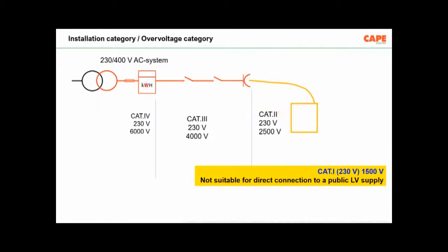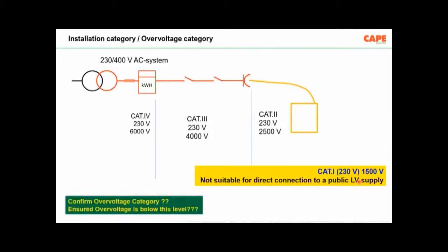That means in your wiring, the minimum category of the equipment is category 3. Connected equipment is category 2. There is equipment called category 1, that means highly sensitive electronics. These highly sensitive electronic devices, we are not supposed to connect directly into a public LV supply, from the transformer. But this is actually the fundamental of protecting electronics or protecting the electrical system.